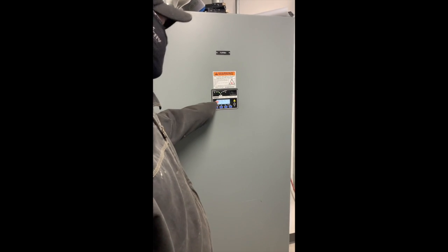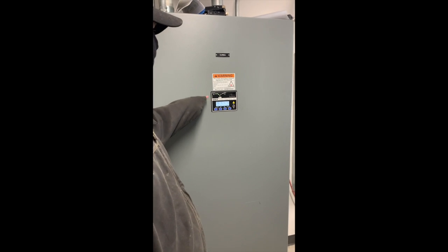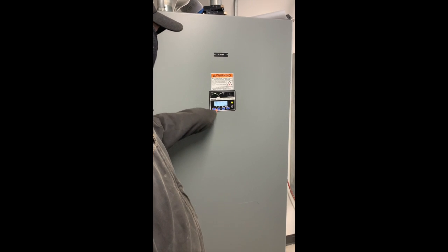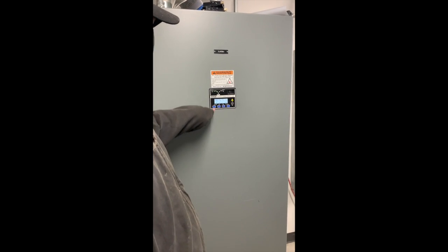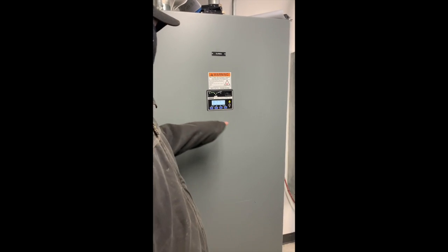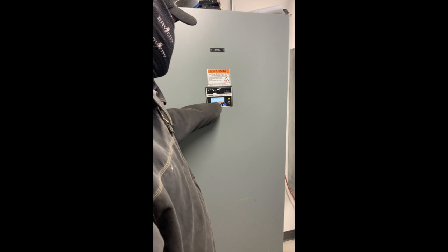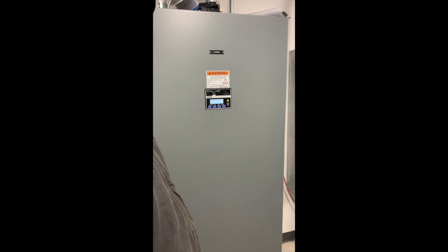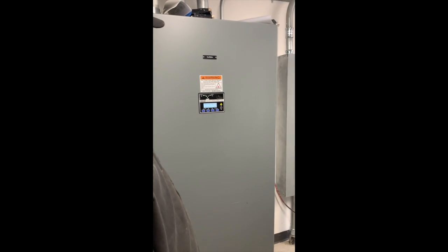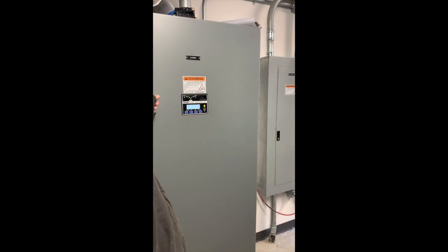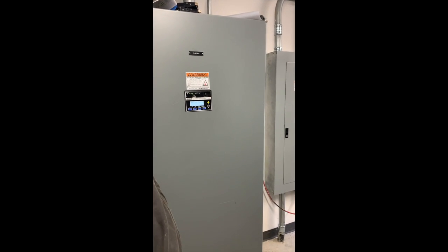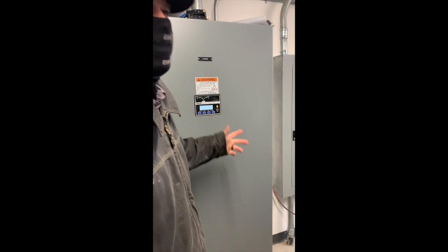This is my PG&E, and then one more down will be the emergency side. This is the generator side. Your voltages will show here, your hertz, and then one more down, again it'll be the same, but on emergency side. Of course, it's 0 because we're not running it. That's your amperage. As long as this one's set up with the amperage reading rings, it will show here. If you don't have that set up, then it'll just say 0.